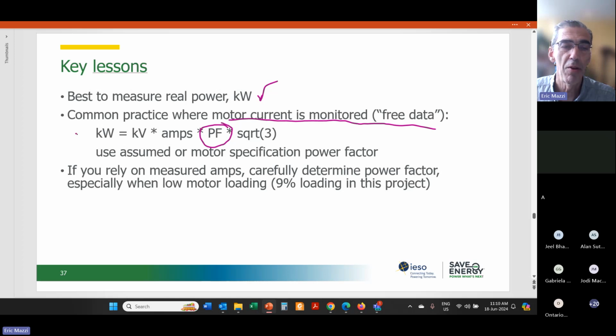So you can just see your real power, even if the amps are correct, 0.85 divided by 0.3, that just meant the real power was overestimated. Let's do the quick math: what's 0.85 divided by 0.25? Yeah, 3.4. So real power was overestimated by a factor of 3.4 using this formula and the incorrect power factor. So the lesson is, if you do rely on measured amps, you want to be very careful about what power factor you use to calculate your real power.